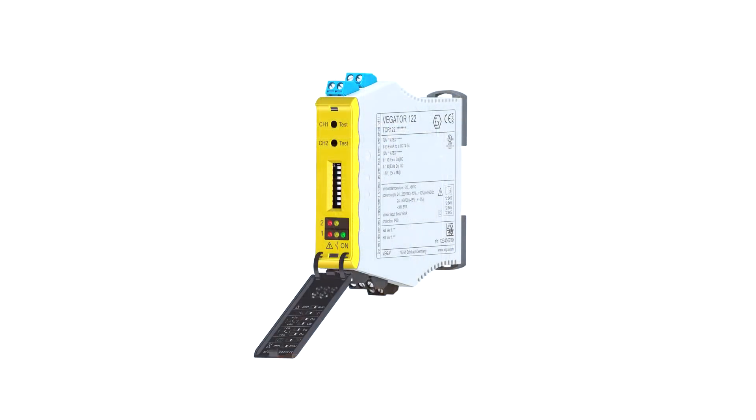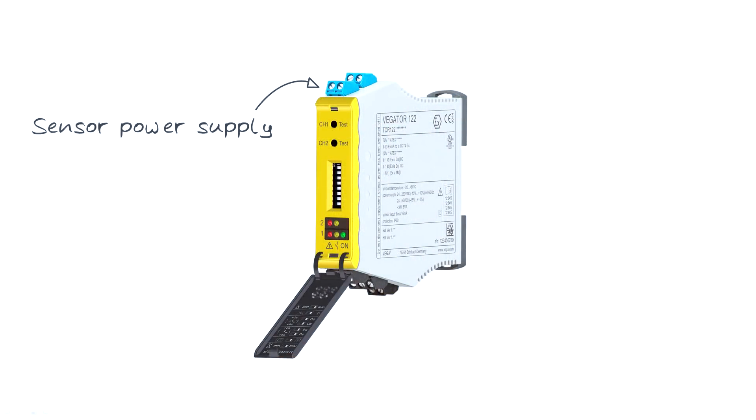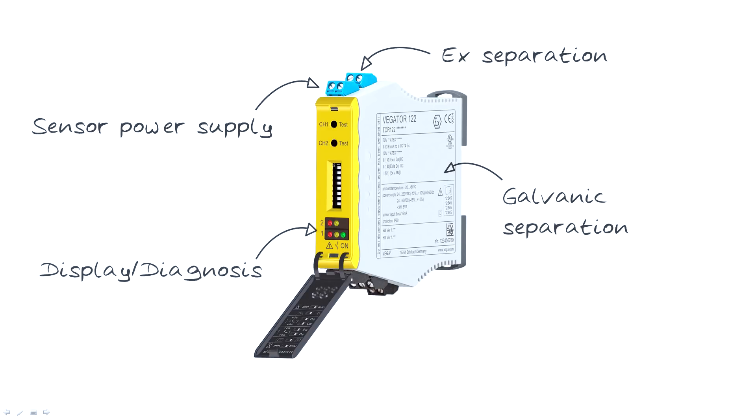First, let's have a look at the task of a signal conditioning instrument. First of all, it supplies the sensor with power and in case of hazardous areas it can also be used as an Ex separator. The inputs and outputs as well as the supply voltage are galvanically isolated. The instrument also provides local display and diagnostic options as well as additional functions such as the function test.